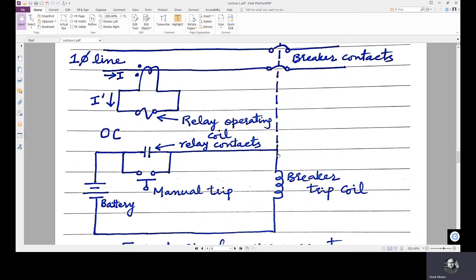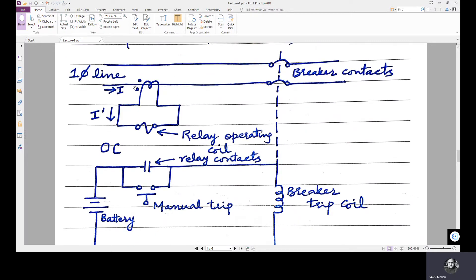The type of instrument transformer used here is a CT. The conductor itself is the primary for the CT, carrying current I in the kilo amps range. The secondary of the CT is the coil shown here, which can be in the form of a ring through which the conductor passes — the power circuit passes — so the ring itself acts as the secondary. The ring circuit is the secondary of the CT, which has I dash flowing through it, and that current operates the relay operating coil. The function of the CT is to reproduce in its secondary winding a current I dash that is proportional to the primary current I.